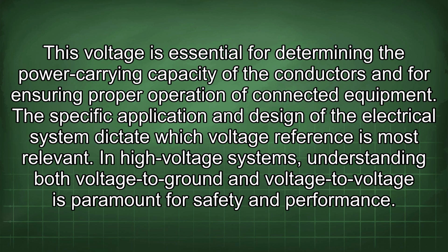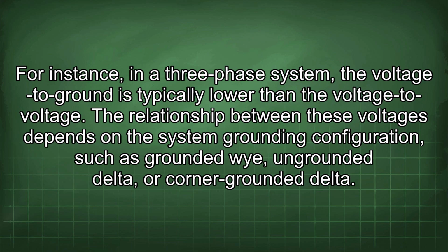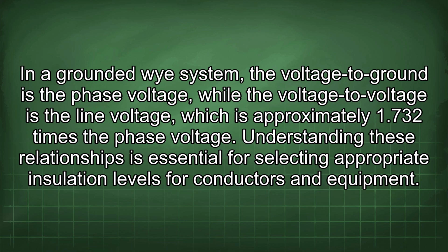In high voltage systems, understanding both voltage to ground and voltage to voltage is paramount for safety and performance. For instance, in a three-phase system, the voltage to ground is typically lower than the voltage to voltage. The relationship between these voltages depends on the system grounding configuration, such as grounded Y, ungrounded delta, or corner grounded delta. In a grounded Y system, the voltage to ground is the phase voltage, while the voltage to voltage is the line voltage, which is approximately 1.732 times the phase voltage. Understanding these relationships is essential for selecting appropriate insulation levels for conductors and equipment.